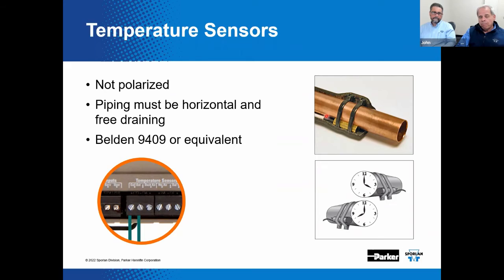Here you can probably get away with zip ties, where we wouldn't recommend that for the bulb for a thermostatic expansion valve. These lightweight sensors can live with that. Yeah. Here we're showing how it would be terminated on the control itself. Right. You're correct. You would not want to do that with a thermostatic bulb, but a lot of the other principles about where to mount them really apply very much the same.